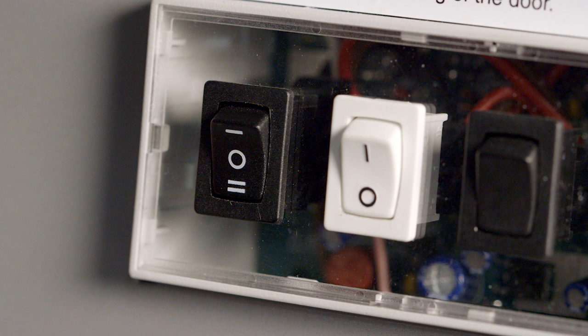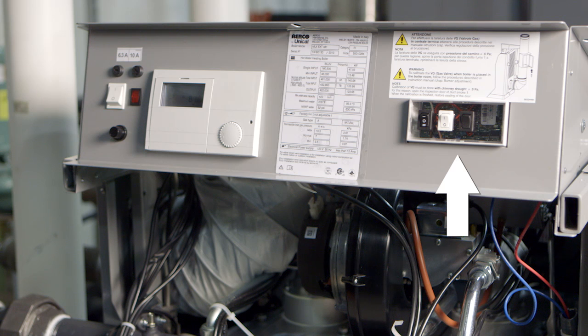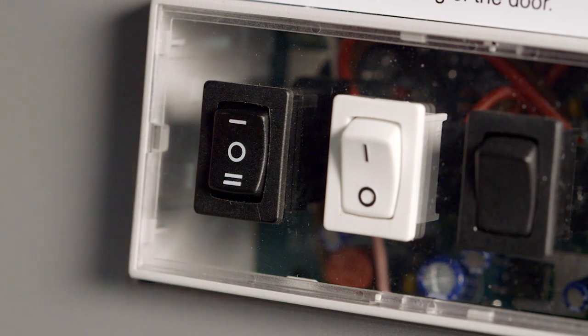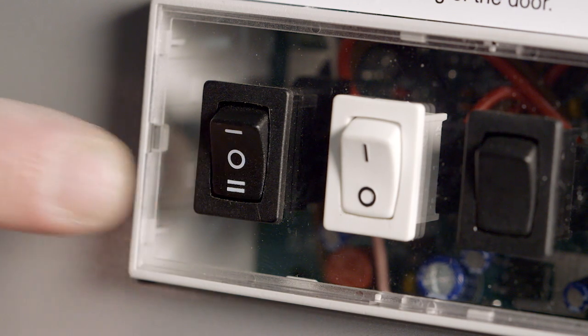Here's how you set the boiler's operating mode and your unit's boiler communication module, also known as the BCM. Your BCM is located here. First, ensure the BCM is set to the correct mode. There is a 3-position switch on the BCM. Position 0 is if your unit is being controlled remotely over Modbus. Position 1 is never used. Position 2 is for local control by the E8.